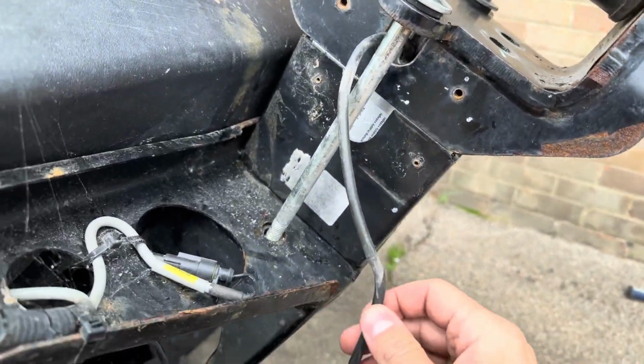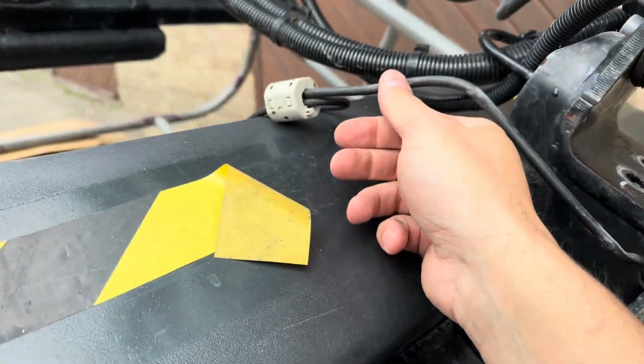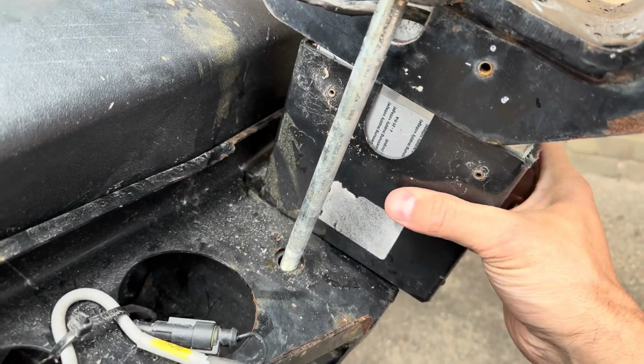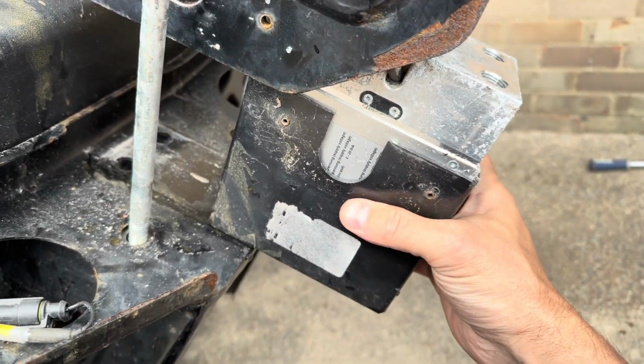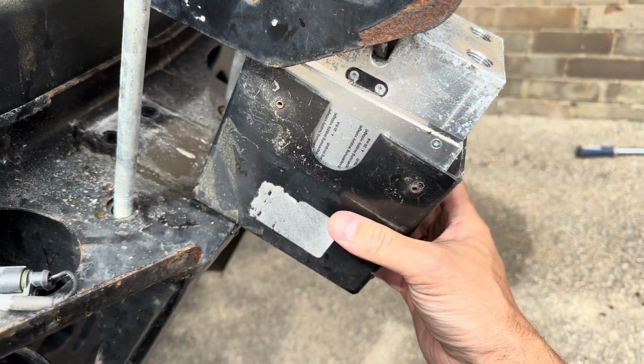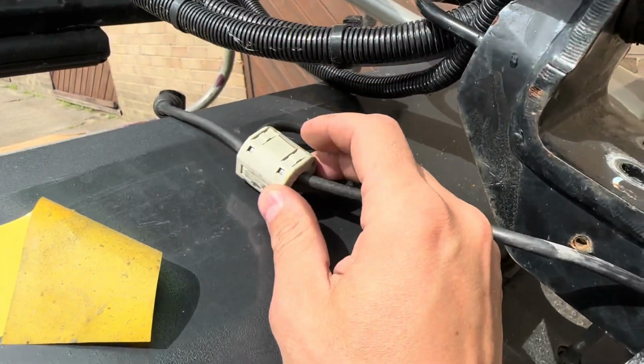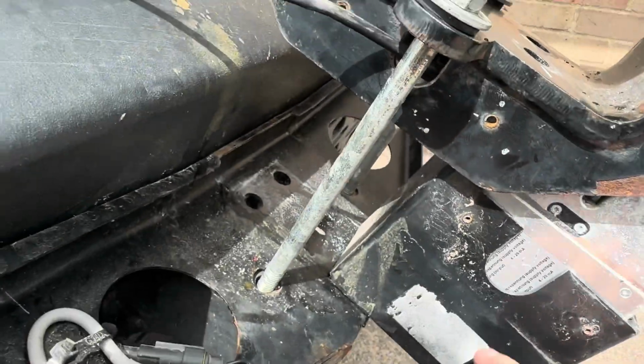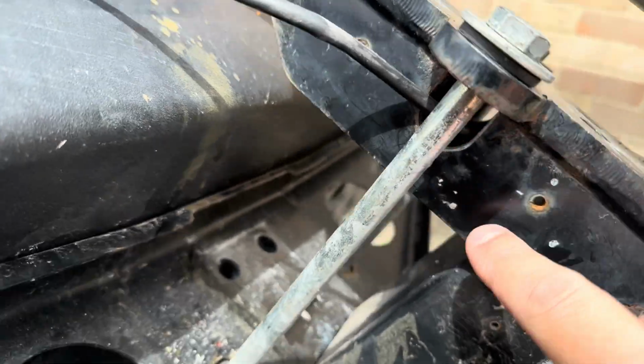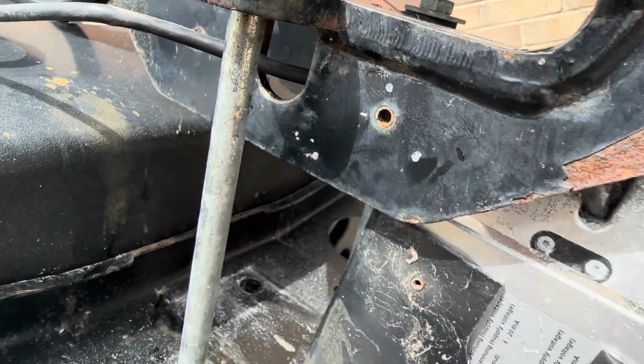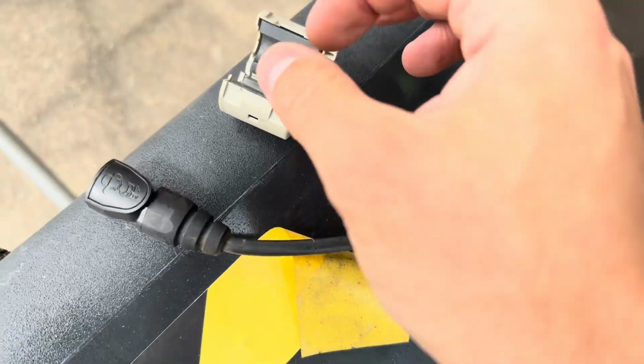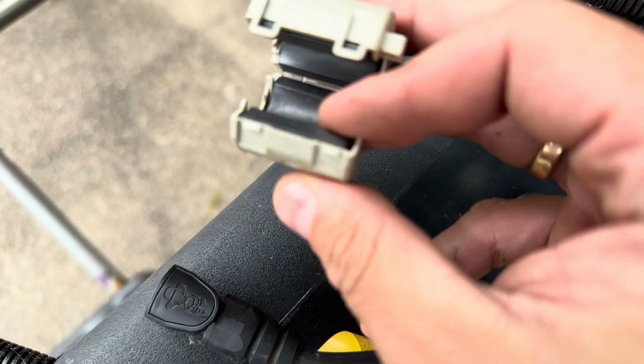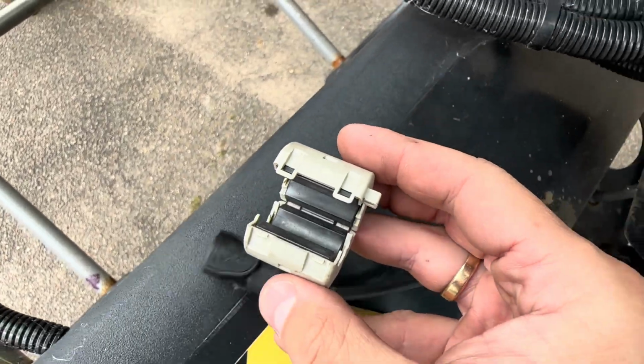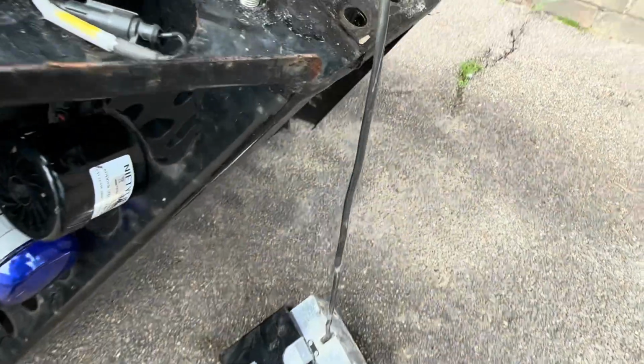So let's try. If I put this cable up on top here and try to slide the load cell out, see, that's coming out, and it will come out. I just need to take this filter off the cable so we can get the connector through that hole right there. That's easy done, just 2 clips holding it together. So you pull the clips, and look, the filter will fall out on its own.